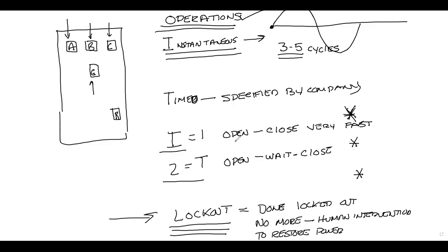A timed operation means open, wait, then close — and you specify this wait time to whatever your company wants. Typically I get one I operation and two T operations. Then the last thing — if the fault still remains on my circuit — you're going to have a condition called lockout. The breaker will give an indication and send a signal to dispatchers: I am now in lockout. Lockout means the device has been isolated and disconnected. No more automatic operations — it's going to take human intervention to restore power.